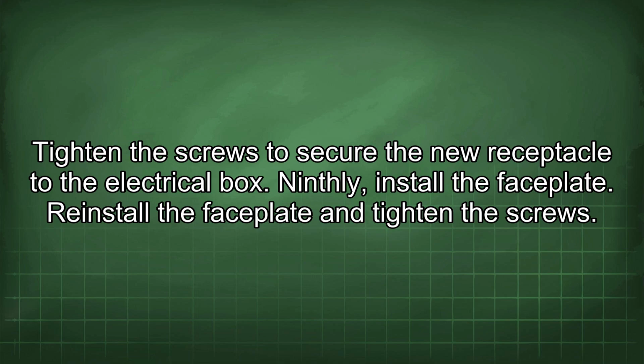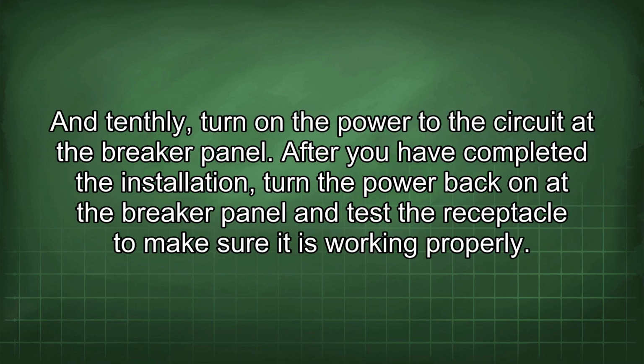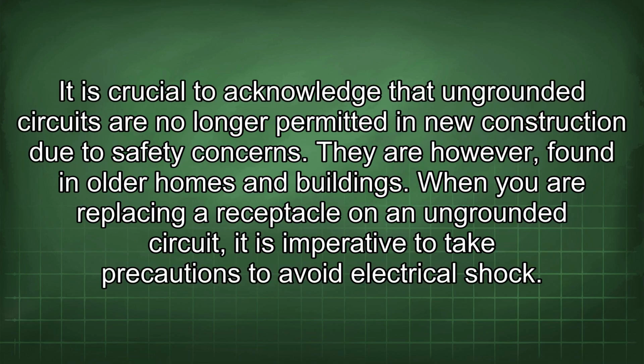Ninthly, install the faceplate. Reinstall the faceplate and tighten the screws. And tenthly, turn on the power to the circuit at the breaker panel. After you have completed the installation, turn the power back on at the breaker panel and test the receptacle to make sure it is working properly. It is crucial to acknowledge that ungrounded circuits are no longer permitted in new construction due to safety concerns. They are, however, found in older homes and buildings.